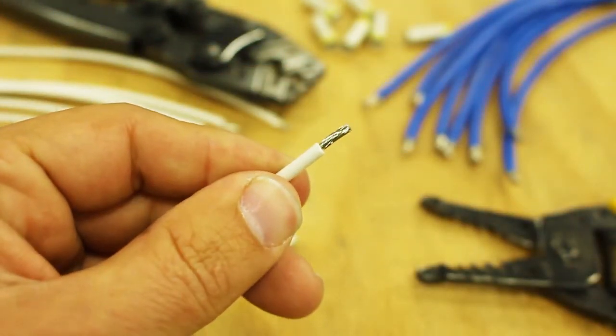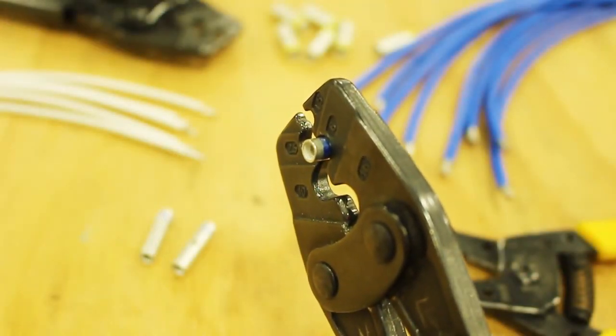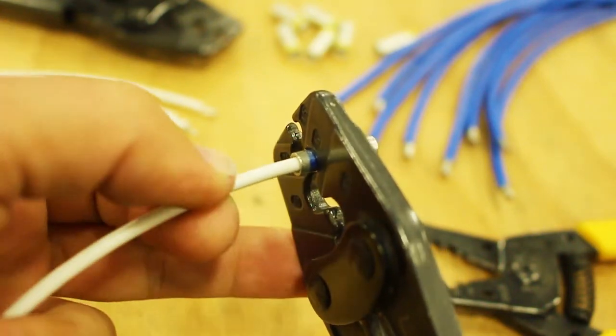The first step is to make sure you have correctly stripped the wires to the proper length. If you look inside the butt splice, you'll see an indentation that your conductors should butt up against. Insert your wire, making sure the insulation touches the connector, otherwise you run the risk of a weak connection.